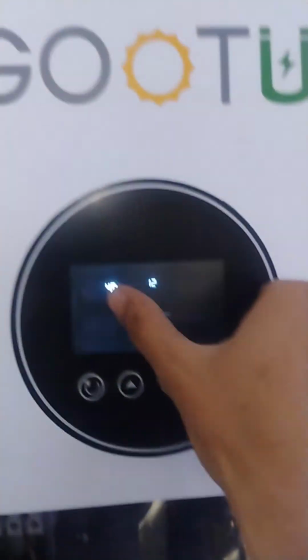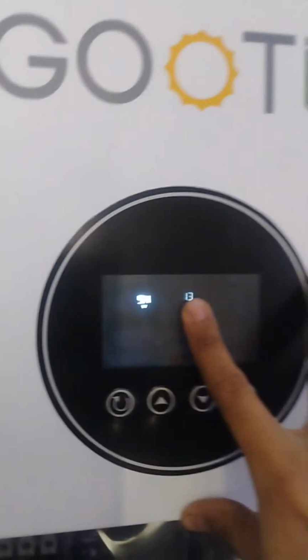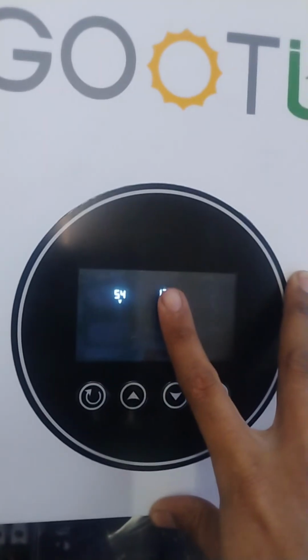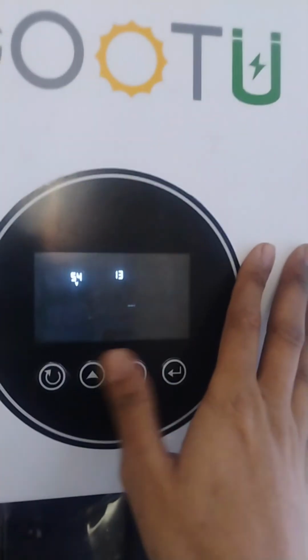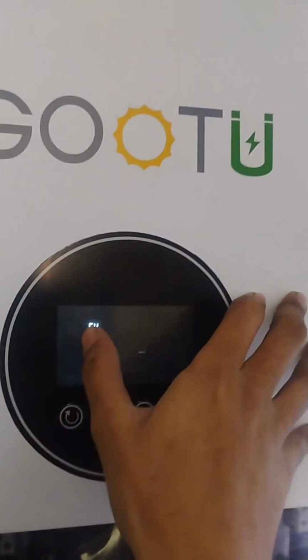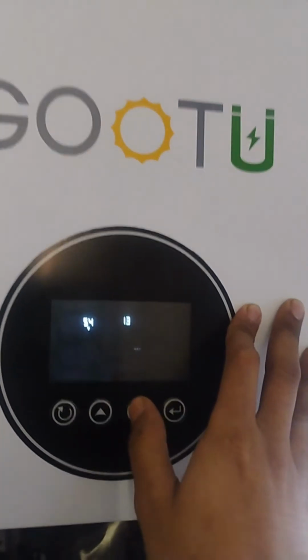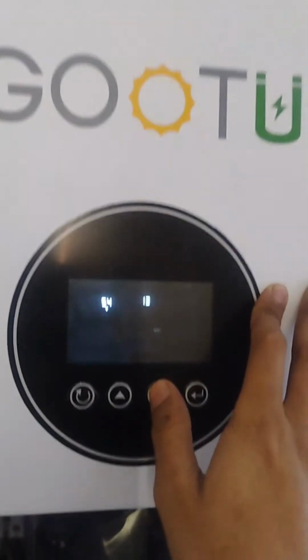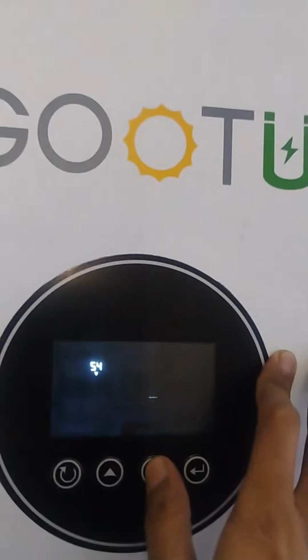The next one is 13 - the setting point to go back to battery mode. When it reaches this volt, after going back to 54 volts, it will automatically switch to grid mode, or you can say the inverter switches back to solar mode or power saver mode when the battery point reaches 54. You can also select around 51 volts, but then you will not be able to utilize the battery power as much - just keep it as default.